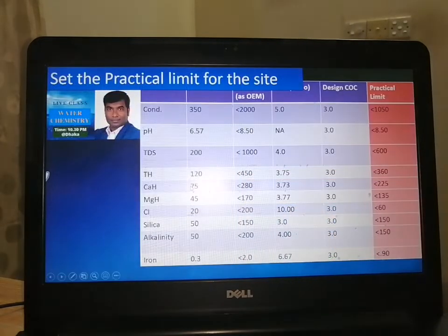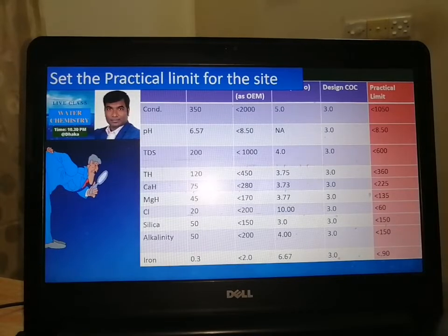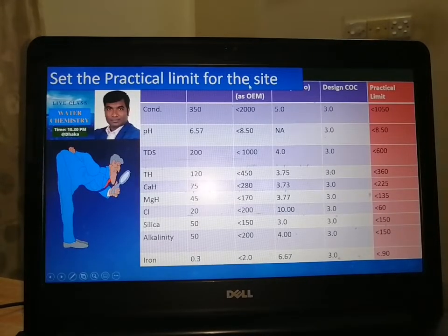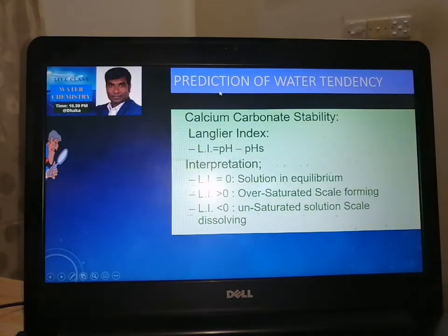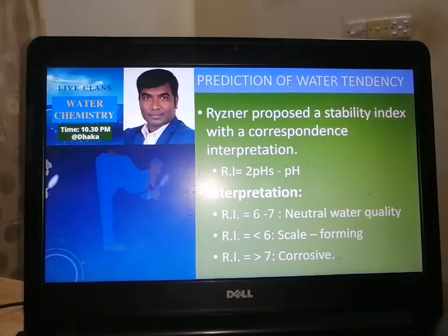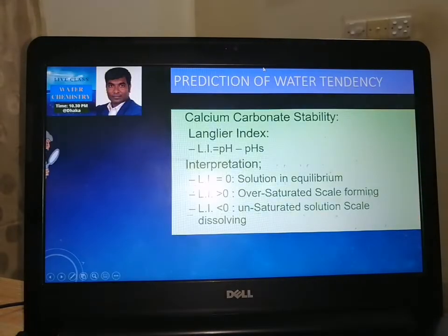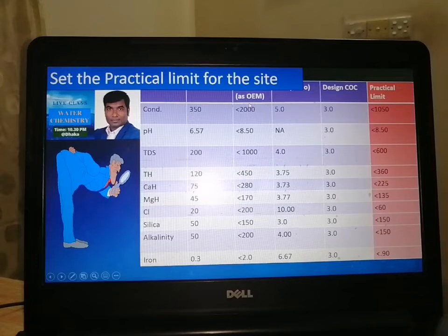Once I have calculated the critical ion, I can set the practical limit for the system. If you see the table here, the same OEM limit is there, but as we found the critical ion is 3, our design cycle of concentration should be 3. So the design cycle of concentration here is 3. If we design our cycle of concentration as 3, then we have to set the practical limit. Our OEM limit of less than 2000 will be okay, but practically we cannot go to that level.